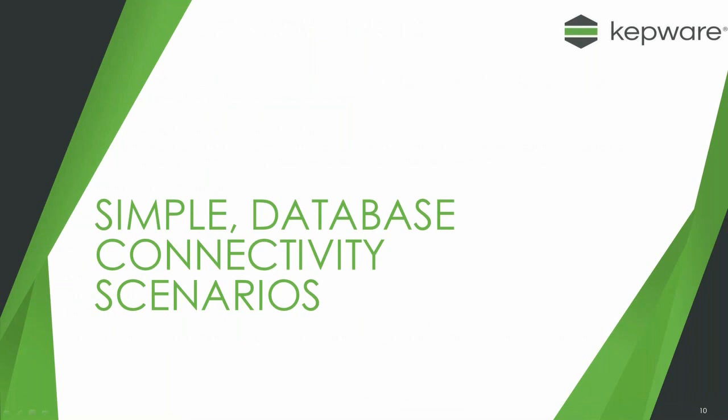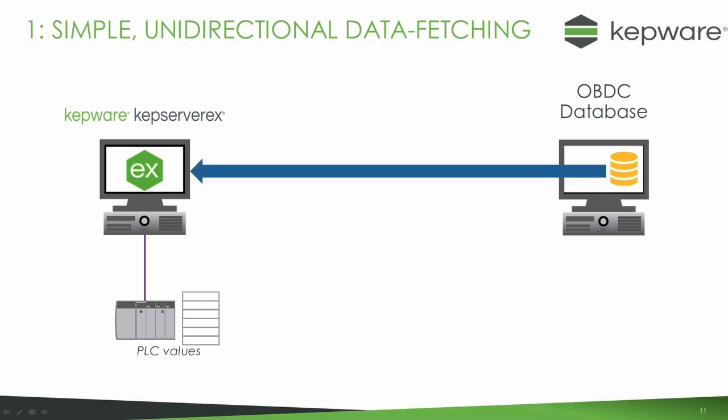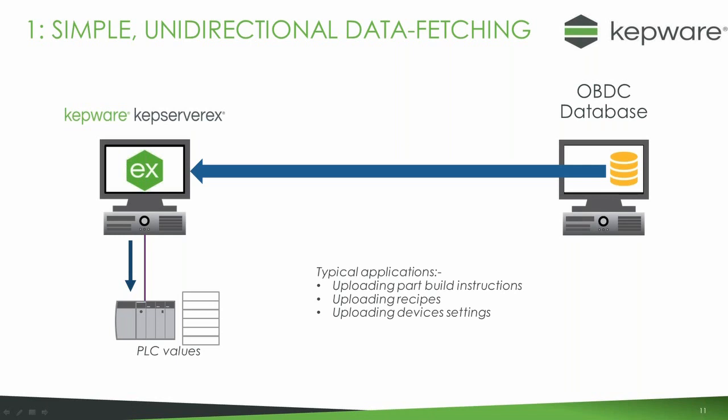Let's look at some scenarios about database connectivity, starting with simple ones. Here we have a database on the right-hand side and KEPServer communicating to a PLC on the left-hand side. The data is coming from the database to KEPServer, and KEPServer is then sending it down to the PLC — a simple unidirectional data fetch from the database down to the PLC. This is typically used for downloading recipes, part build instructions, or settings for the devices or machine.